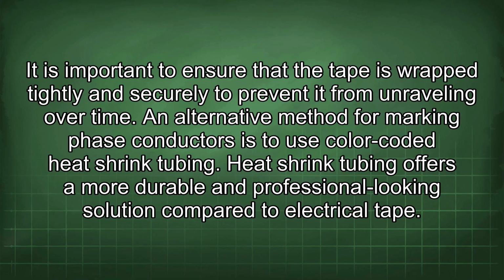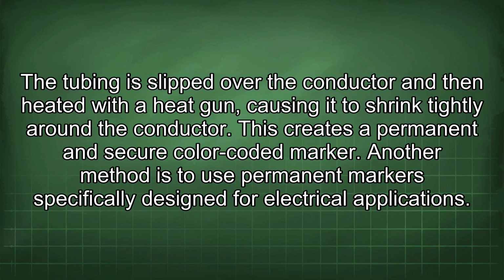An alternative method for marking phase conductors is to use color-coded heat shrink tubing. Heat shrink tubing offers a more durable and professional-looking solution compared to electrical tape. The tubing is slipped over the conductor and then heated with a heat gun, causing it to shrink tightly around the conductor. This creates a permanent and secure color-coded marker. Another method is to use permanent markers specifically designed for electrical applications.